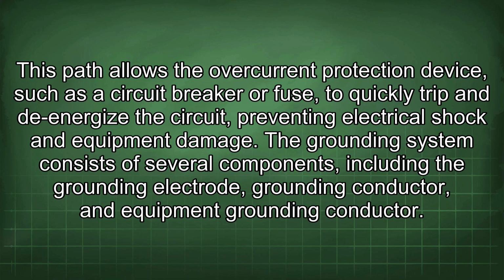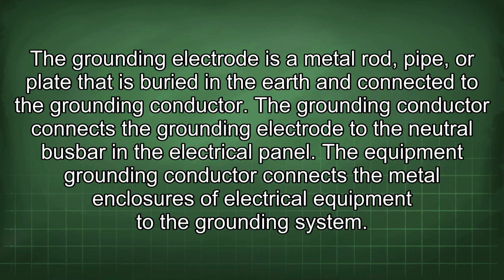This path allows the overcurrent protection device, such as a circuit breaker or fuse, to quickly trip and de-energize the circuit, preventing electrical shock and equipment damage. The grounding system consists of several components, including the grounding electrode, grounding conductor, and equipment grounding conductor. The grounding electrode is a metal rod, pipe, or plate that is buried in the earth and connected to the grounding conductor. The grounding conductor connects the grounding electrode to the neutral busbar in the electrical panel. The equipment grounding conductor connects the metal enclosures of electrical equipment to the grounding system.